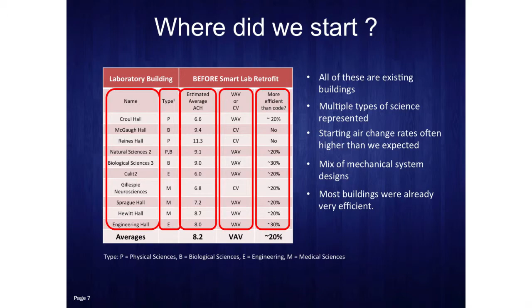Constant volume or variable volume—where did we start? It's important to know we've done both types of retrofit. And as Wendell also indicated, these buildings started more efficient than code—some as LEED Gold, some as LEED Platinum—and we still went in and did retrofits. So just because you've reached the USGBC point total doesn't necessarily mean you have the most energy efficient lab building you can possibly operate.